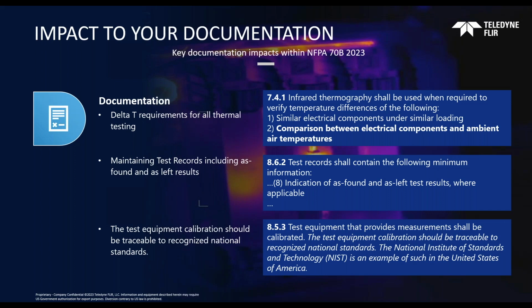Maintaining those records includes as-found and as-left results. Section 8.6.2 gets into what actually needs to be included in a test record. There's a series of about 12 specific line items, but the one I'm calling out here is indication of as-found and as-left test results where applicable.